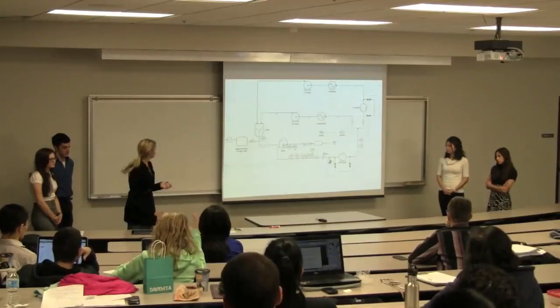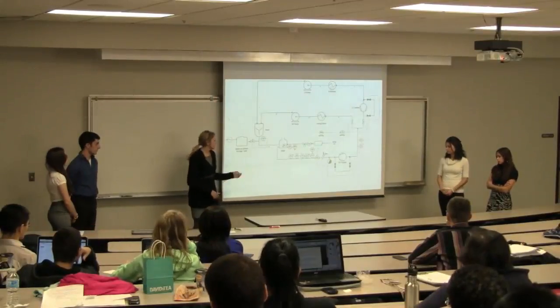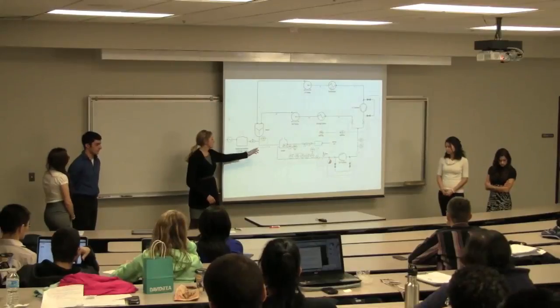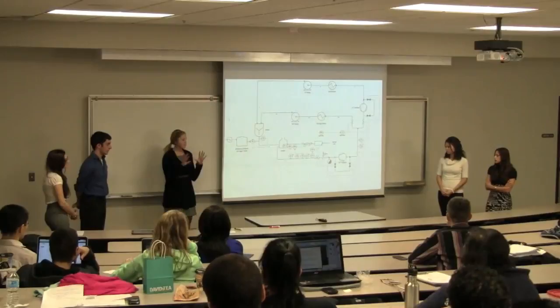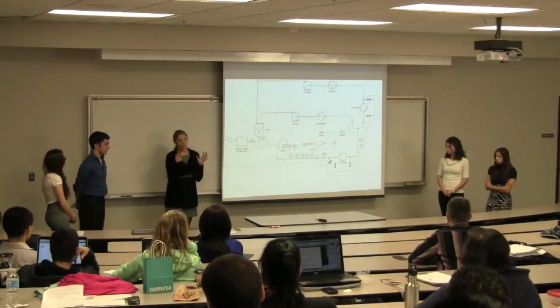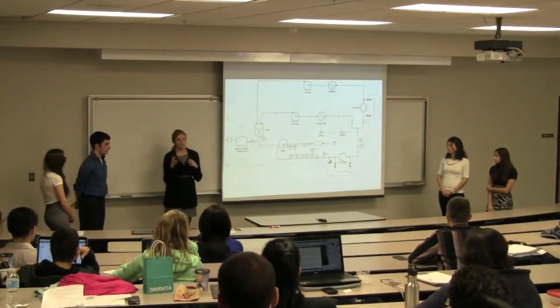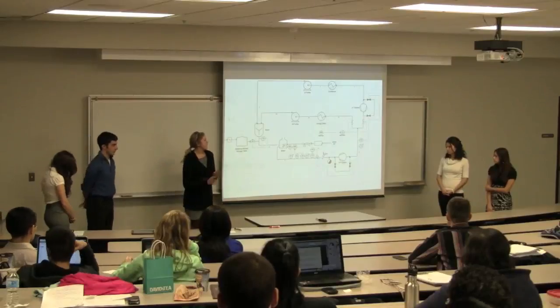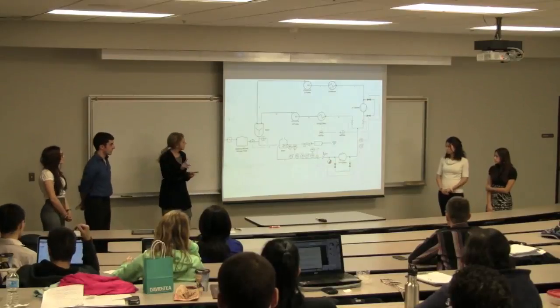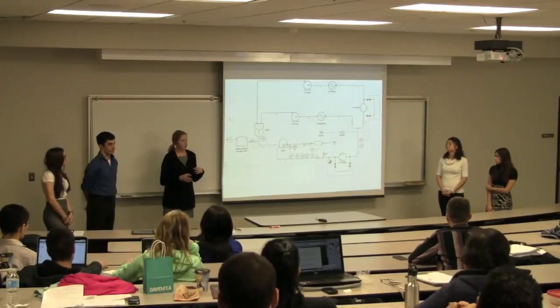So just briefly, here's the diagram again. Our startup is pretty standard. You're just going to start generating some steam with your boiler and then bring it into your turbine. You're going to try and heat up that pipe first with your vents and drains open to about 80 to 85% of the actual operation temperature, and then you're going to start ramping up your turbines, closing all those drains and vents, and slowly ramp up the actual LP turbine, and once you get to enough capacity, then you can bring your energy plant online.